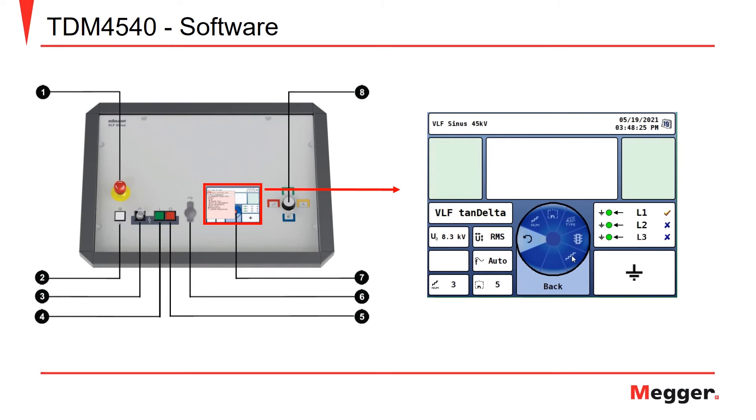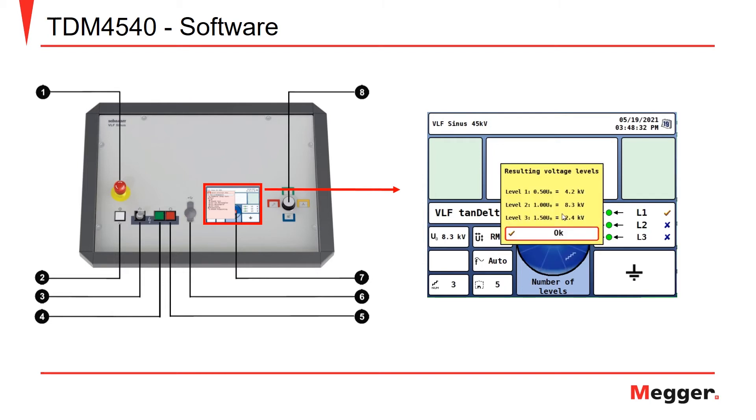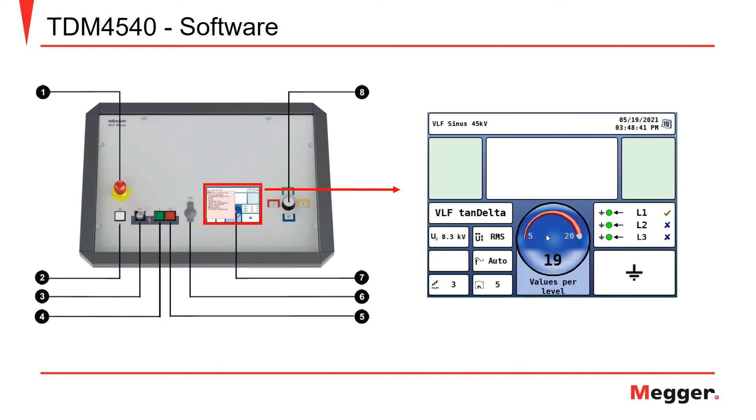Next, we can look at our test parameters, where we have the number of levels we would like to step, anywhere from 1 to 6. We'll leave it at 3. This is our resulting voltage levels, which has stayed the same. The number of values per level can be 5 measurements per level, all the way up to 20 measurements per level. We'll leave it at 5 for this test.